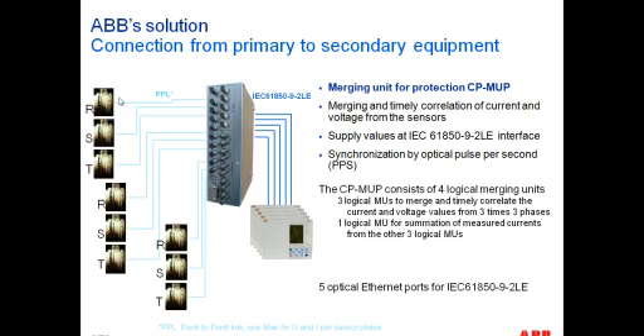Okay, and this is just a basic view. You could have up to three-phase sets of analog quantities into our merging unit, and then there are 5 independent Ethernet ports to feed information for up to 5 different relays. The time synchronization used by the merging unit is essentially based on PPS, just like the 61850-9-2LE implementation guidelines from the UCA group prescribed.